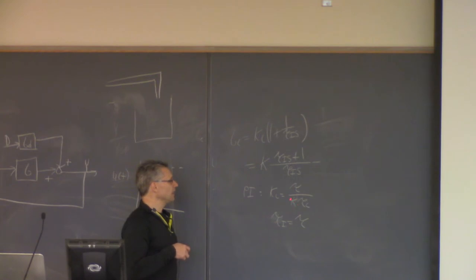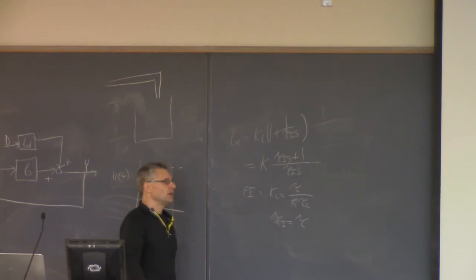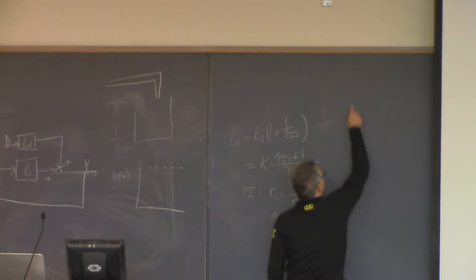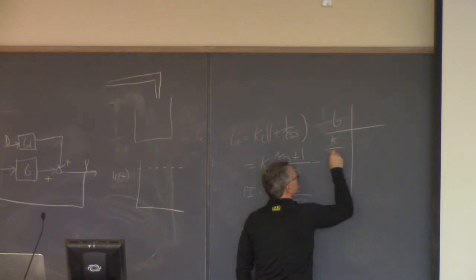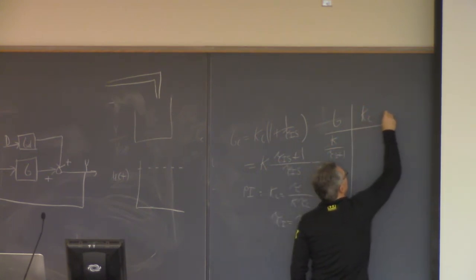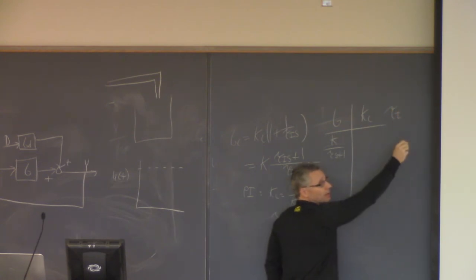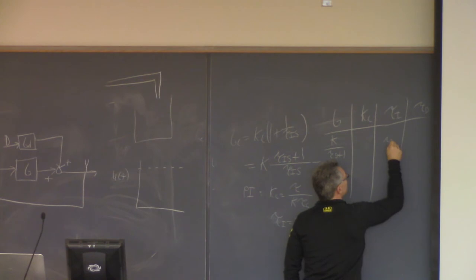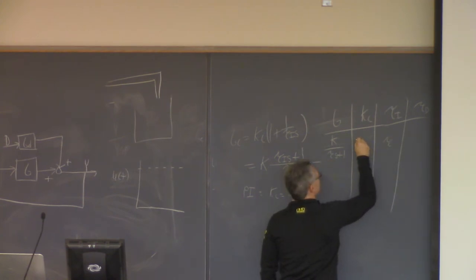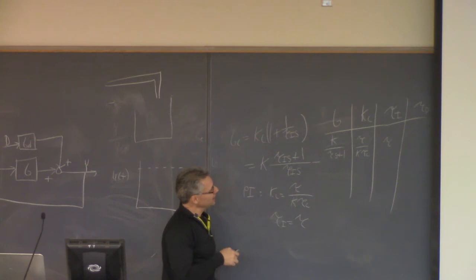So this is another way to tune a PI controller. If you have the first-order transfer function available, you know K and tau. You pick tau_c, and now you have Kc and tau_i values — you have a PI controller. In the book, Table 12.5 has a whole table of these formulas: for this transfer function, Kc equals tau/(K * tau_c) and tau_i equals tau.